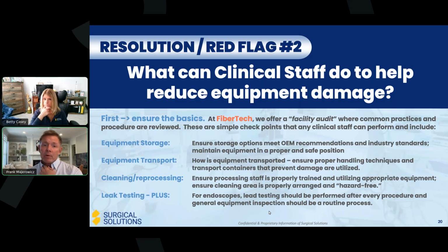But certainly the first area is equipment storage. Again, whether it be a flexible scope, a rigid scope, everything needs to be stored properly. And if it's not stored properly, it's an area where damage could be occurring. For example, flexible endoscopes typically hang in closets. Over the years, there's lots of occasions where you would go in and the closet's just not high enough off the ground, the rack, and the tip of the scope is hanging on the ground. It's not what you want to see. It's an area that damage could cause, and fluid can collect down there. It might not drain properly. It could cause different issues.